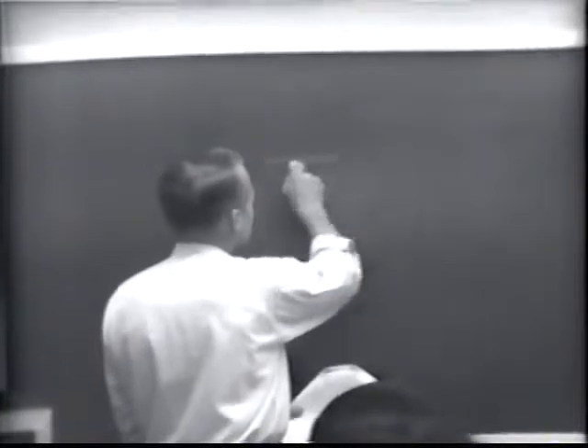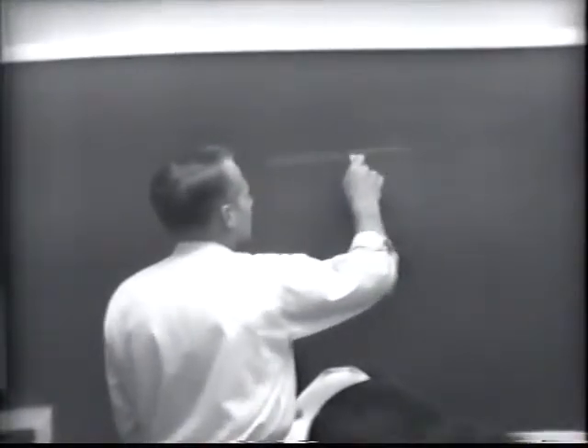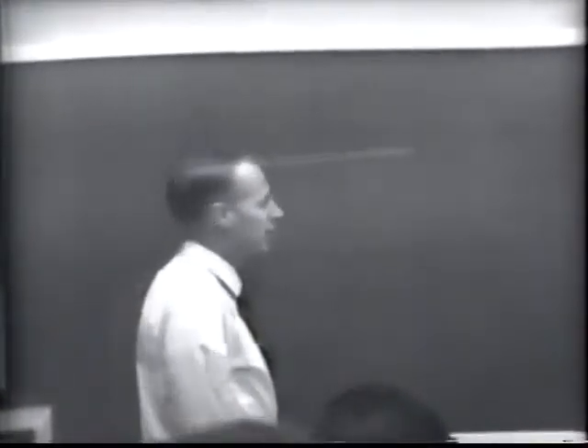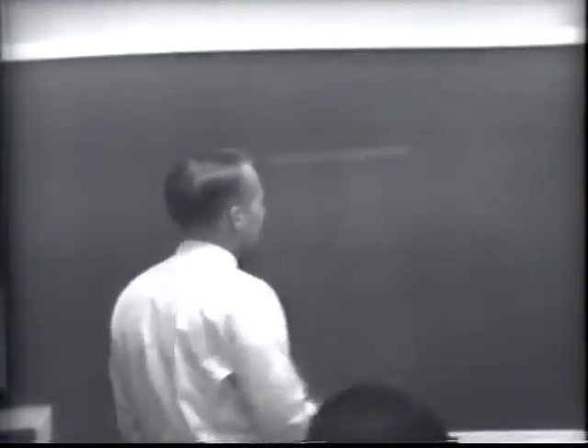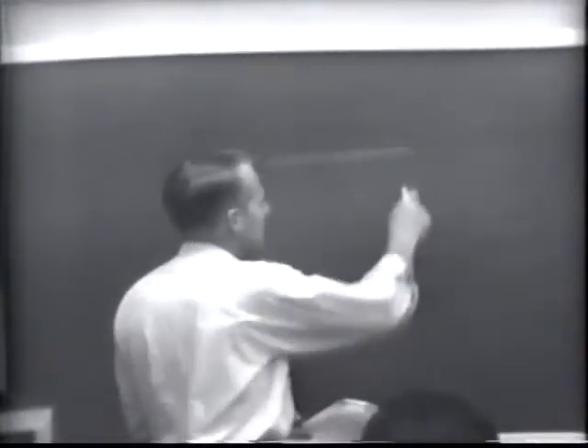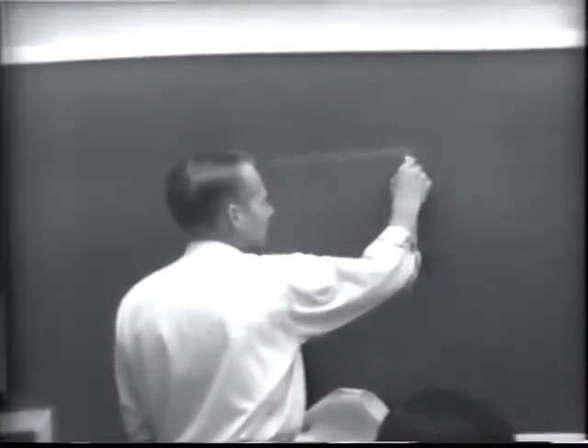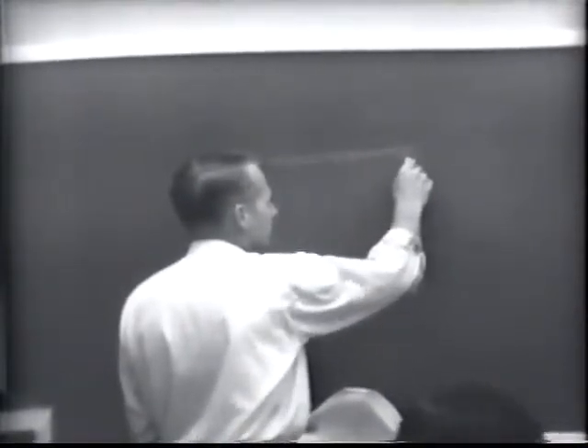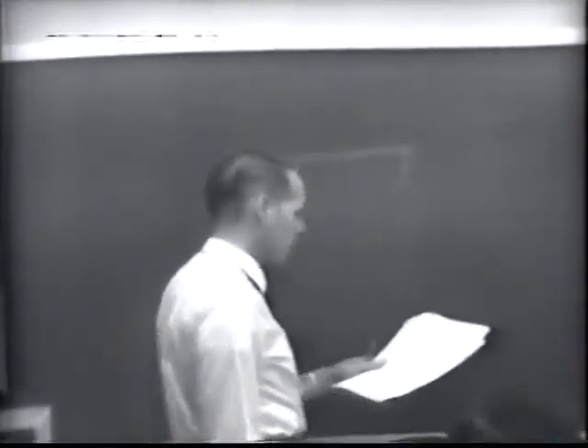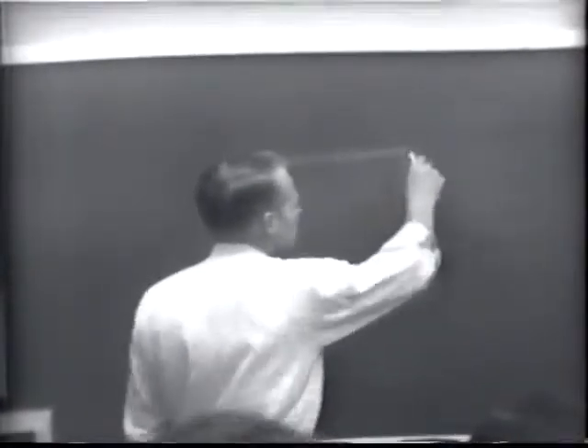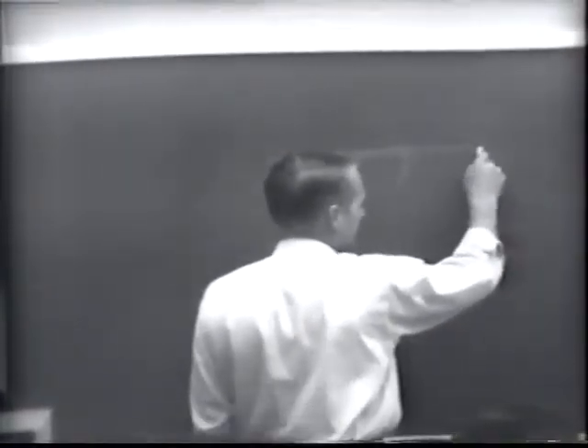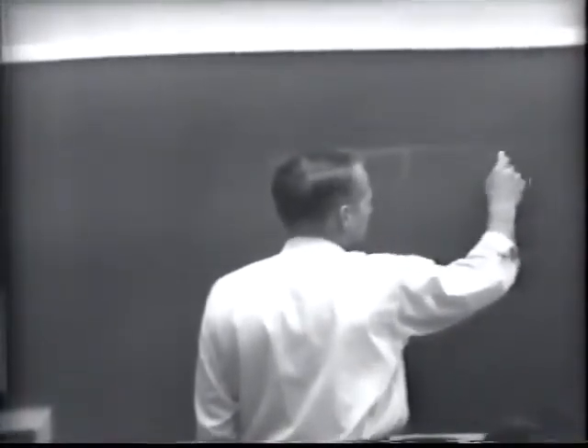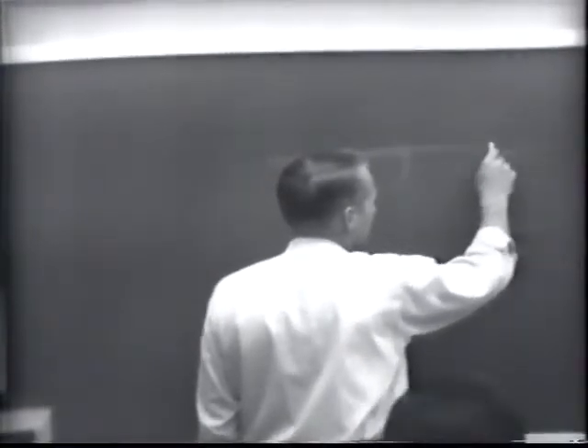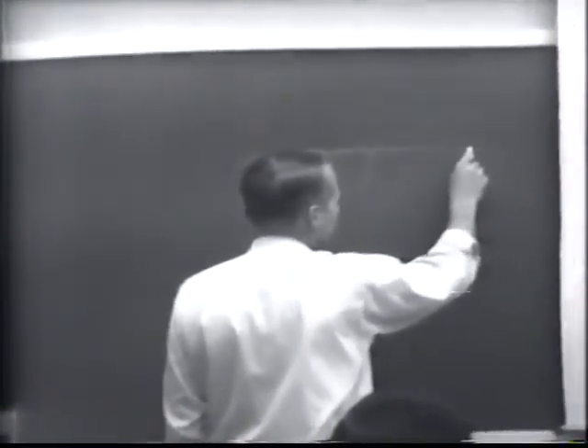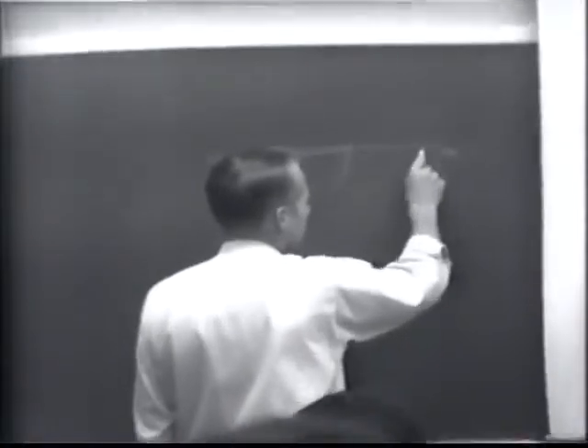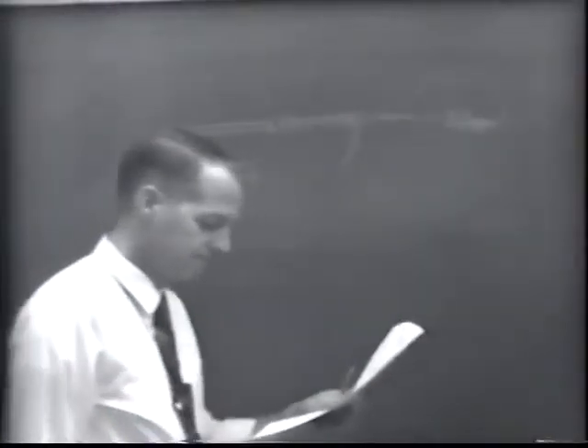If we have two pieces of tubing here and we want to connect them, we'd have a straight connector there. Another type would be a T-tap, where we want to tap this tubing and bring another piece of tubing or conductor off like that. If this tubing were to extend onto a disconnect switch, it has a pad here, so we'd have a connector that would bolt to the pad and at the same time bolt to the end of the tubing.